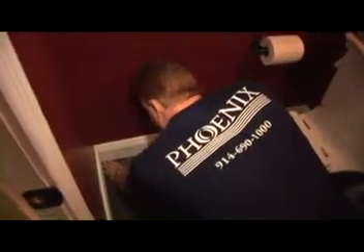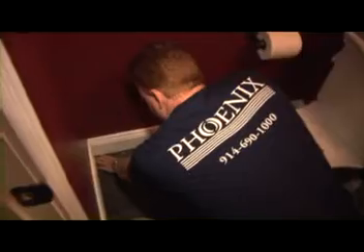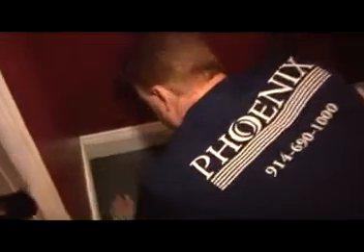Initially, there wasn't an obvious reason for airflow. When I got down to the floor to feel around the baseboard, I can feel cold air rushing in from underneath the baseboard molding. So there's probably some kind of ceiling penetration in the basement that's allowing air to get up into the floors and into the bathroom here.